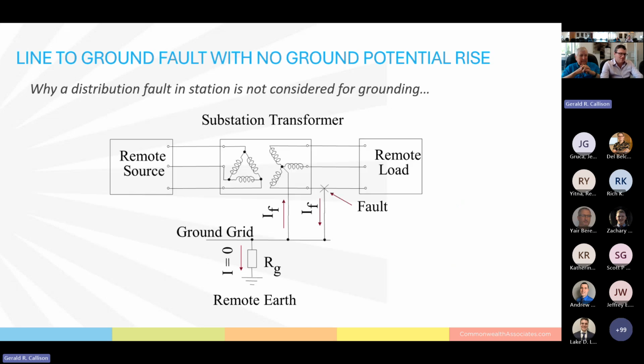Now, a little more about ground potential rise. There are some faults in a station that are not going to produce significant ground potential rise, and therefore we don't really look at them when we're studying grounding system design. A lot of those faults occur on a distribution bus in a substation, and that's because the distribution bus is fed from a grounded Y winding of a transformer.